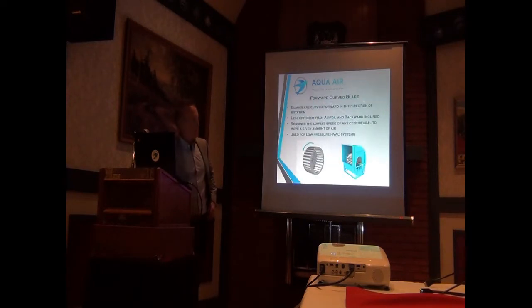When we talk about forward curve fans, it's probably the most used fan in the HVAC industry over the decades. It's been your standard forward curve fan. It looks like this, like we said, with your standard housing here. The blades are curved forward in the direction of rotation of air, and it kind of scoops air with that forward curved blade. Less efficient than an airfoil and backward inclined fan. Requires the lowest speed of any centrifugal fan to move a given amount of air. Used for low pressure HVAC systems.